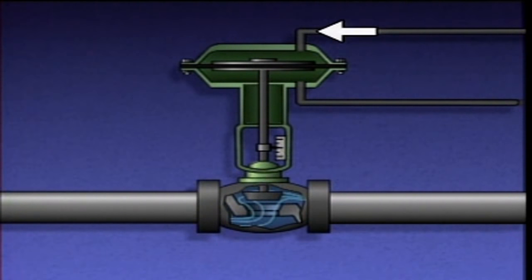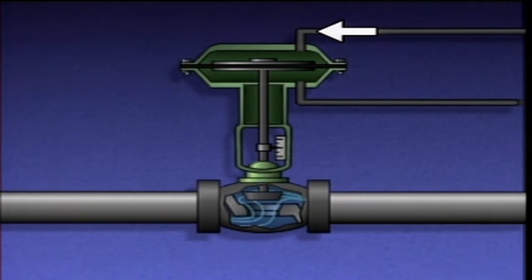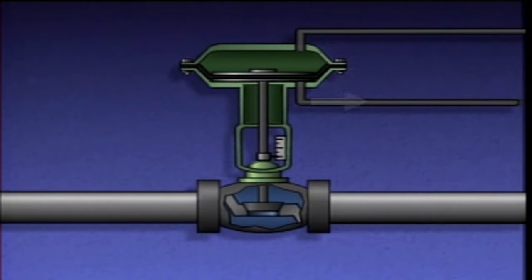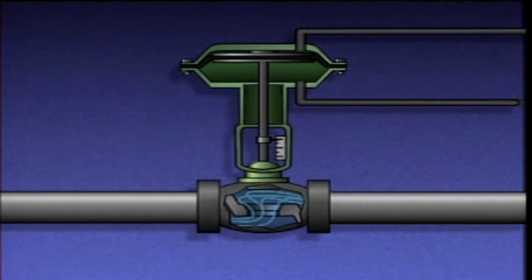When air pressure is applied to the upper chamber, the diaphragm and the actuator stem are pushed downward and the valve closes. Air in the lower chamber is exhausted through the lower air supply port. When air pressure is applied to the lower chamber, the diaphragm and the stem are pushed upward and the valve opens.